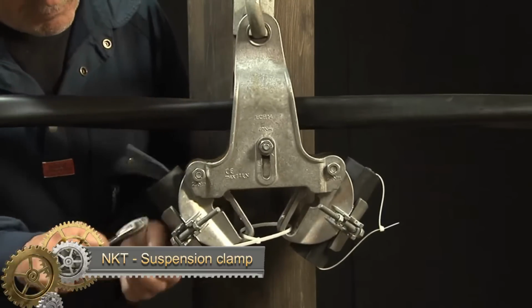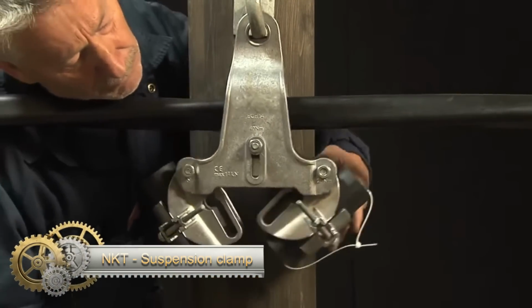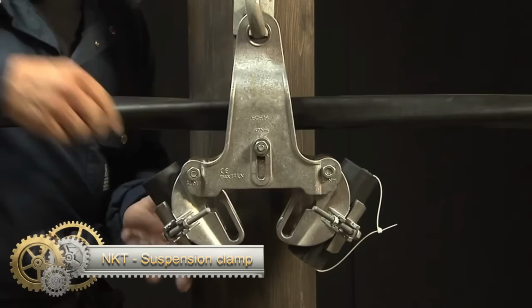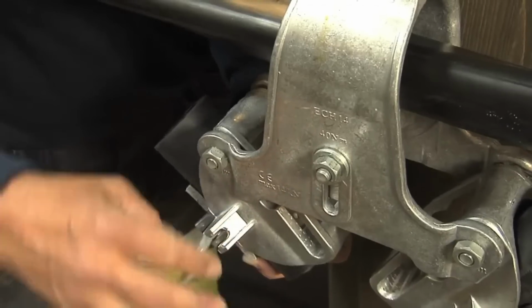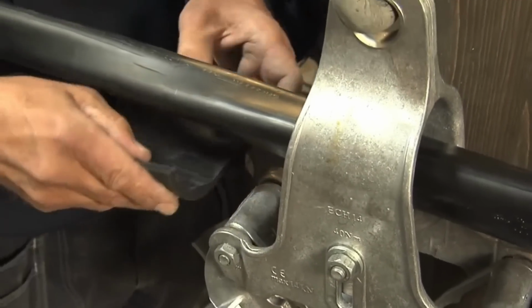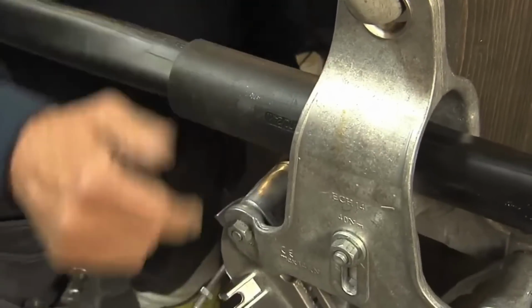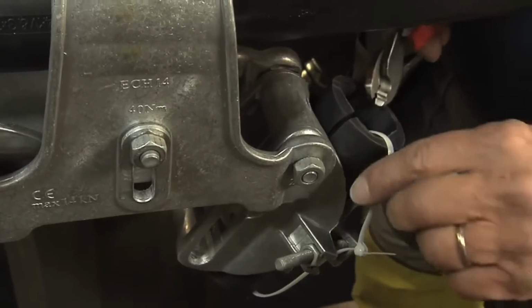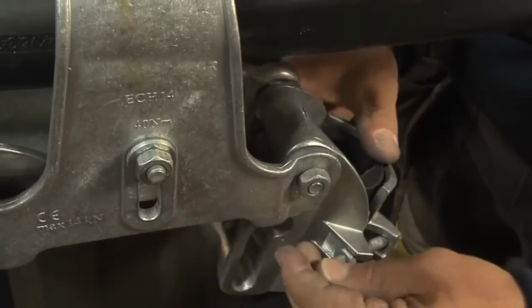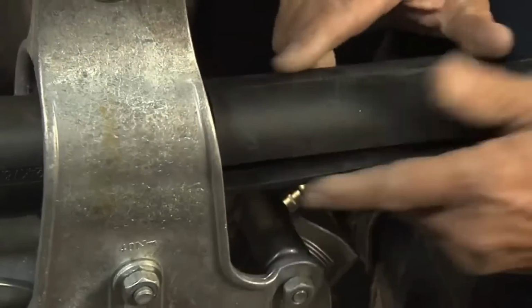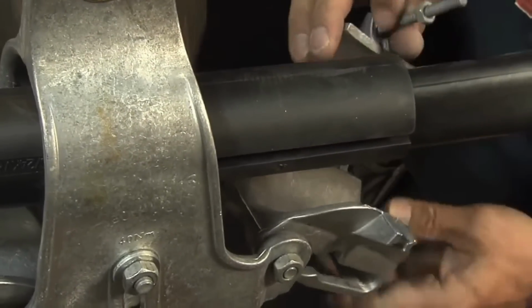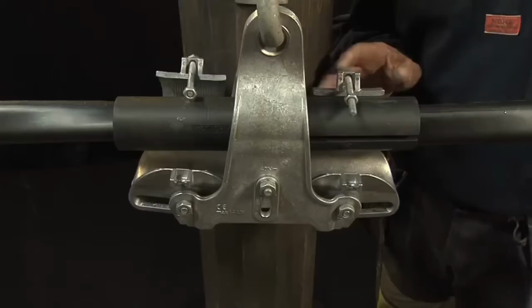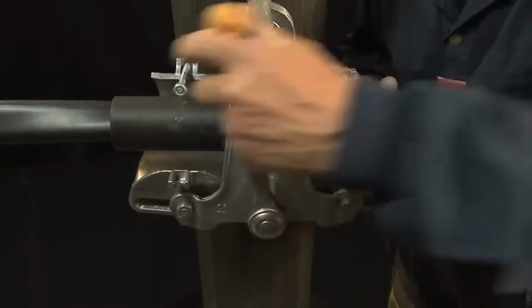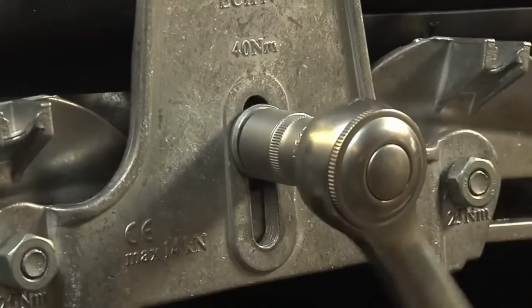The ECH14 suspension clamp, integral to the universal cable system for ADSS cables, ensures secure overhead cable suspension. Begin by opening the clamp fully by counterclockwise rotation of the wedge. Insert the cable into the clamp groove, centering it properly, and then tightly close the clamp by rotating the wedge clockwise, engaging its teeth for a firm grip.